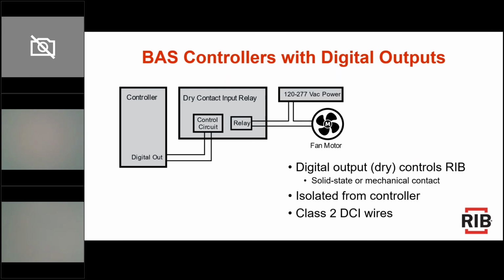Well, our dry contact input relay can be connected to that, and that would be able to send that signal to the control circuit to then have that relay turn on a 120 volt fan motor. So obviously you can't connect the 120 volts to the controller unless you want to buy a new $1,000 controller. But our RIB dry contact input relays are the great middleman to take that signal from the controller and switch on and off that fan motor. Again, the class 2 dry contact input wires, it's a big deal.